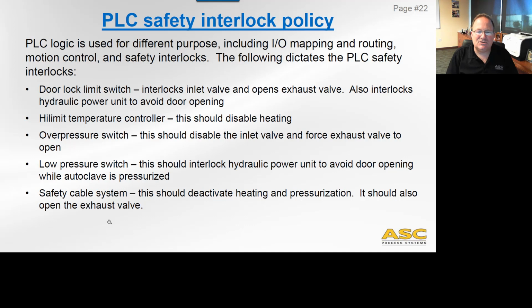The PLC logic is used for different purposes, including IO mapping and routing, motion control, and safety interlocks. The following dictates the PLC safety interlocks that are going to be used. So door lock, limit switch interlocks inlet valve and opens exhaust valve. Also interlocks hydraulic power unit to avoid door opening.